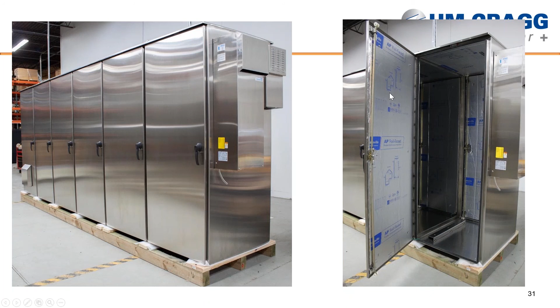The customer worked with us to design the footprint of the enclosure, the number of doors, and all the mounting points for the battery racks that are going to be installed. We also insulated the enclosure, adding foil-backed insulation, about 1 inch thick, mission venting, air conditioning, and a hydrogen sensor to the design. That was the limit of our work on this particular project.